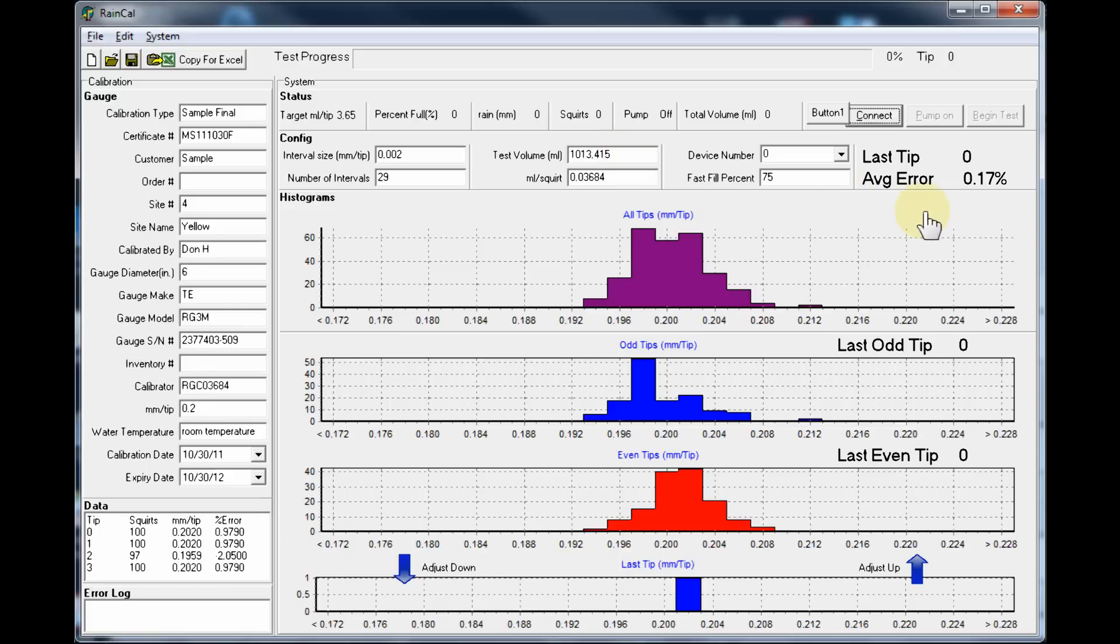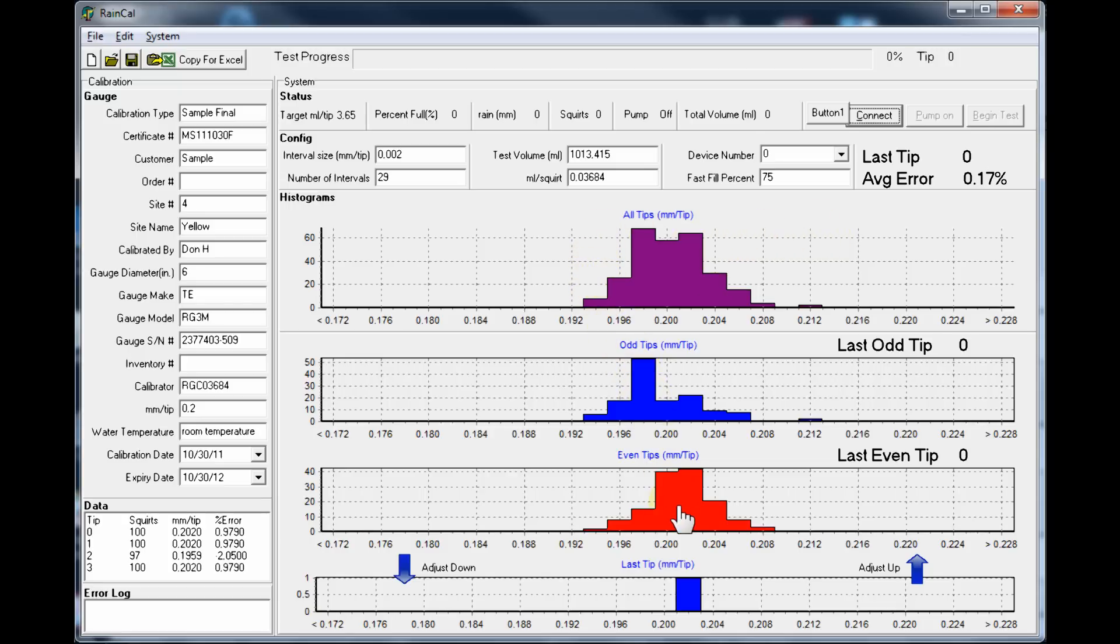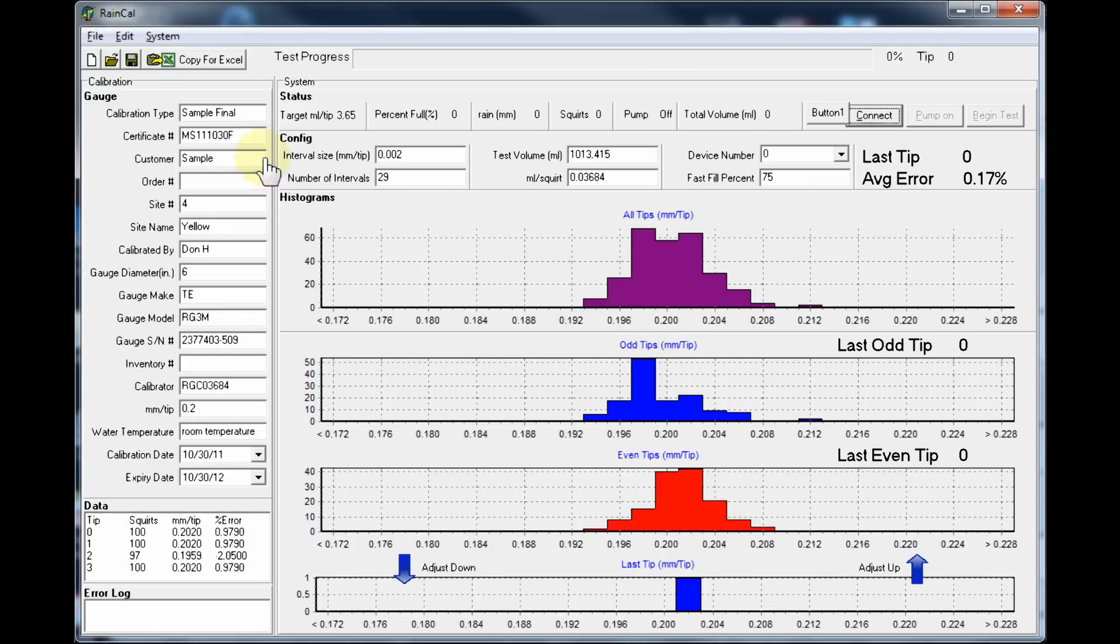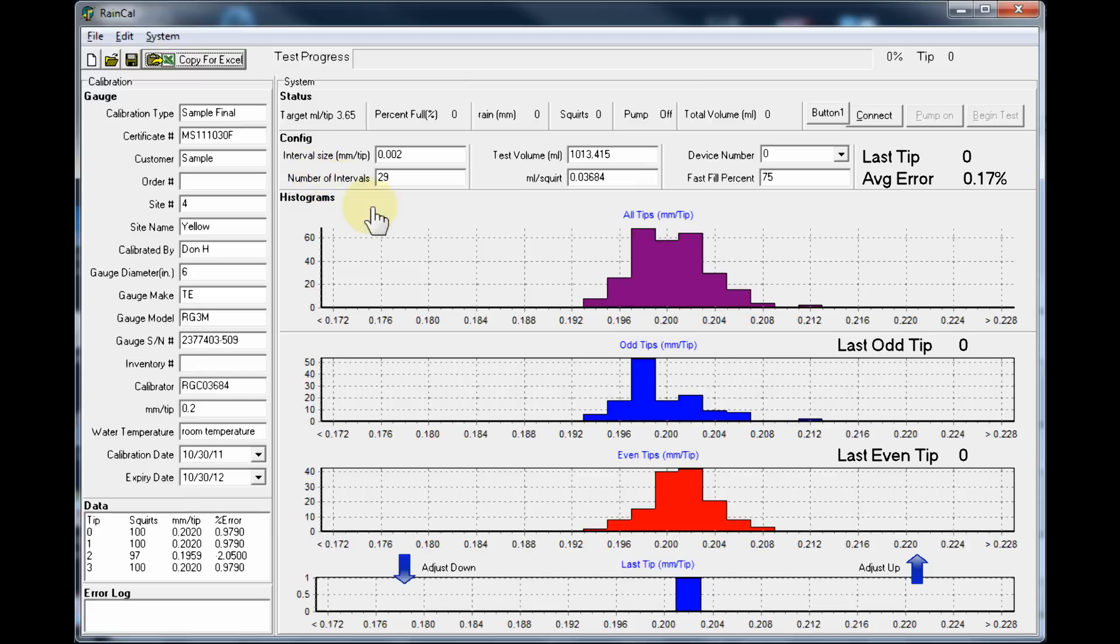After the gauge is adjusted and about one liter of water is put through the calibrator and the rain gauge, the net result is about 0.17% error on this particular gauge. This histogram here is a combination of both the left and right histograms, and that is the data that will be sent to the calibration certificate. The information can be copied to a clipboard with this button here, and then the data can be pasted into an Excel file which generates the calibration certificate.